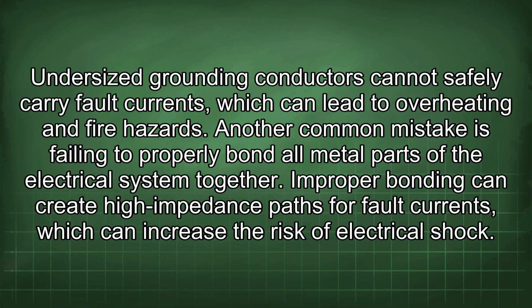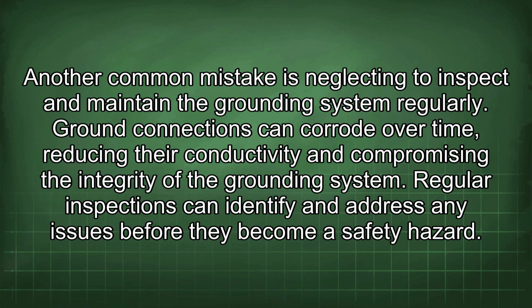Another common mistake is failing to properly bond all metal parts of the electrical system together. Improper bonding can create high impedance paths for fault currents, which can increase the risk of electrical shock. Another common mistake is neglecting to inspect and maintain the grounding system regularly. Ground connections can corrode over time, reducing their conductivity and compromising the integrity of the grounding system. Regular inspections can identify and address any issues before they become a safety hazard.